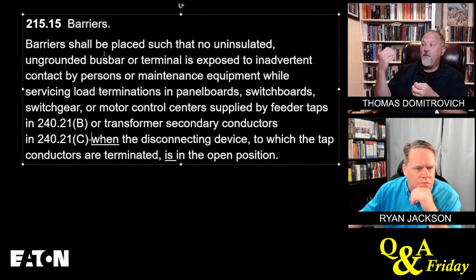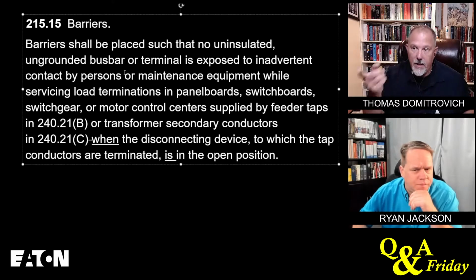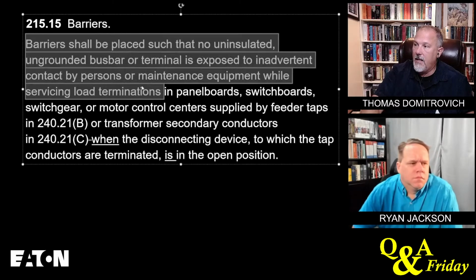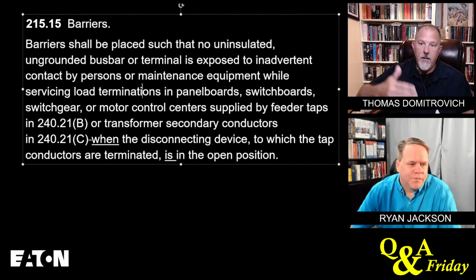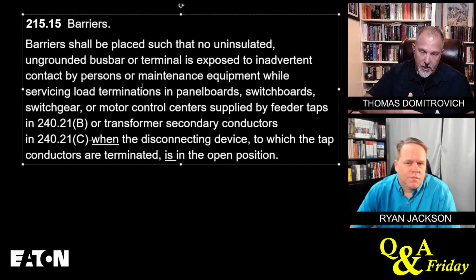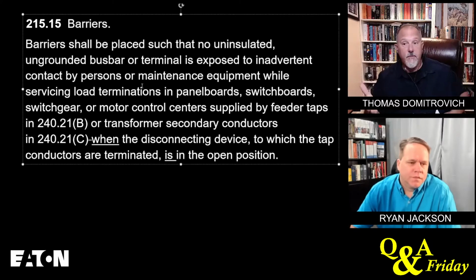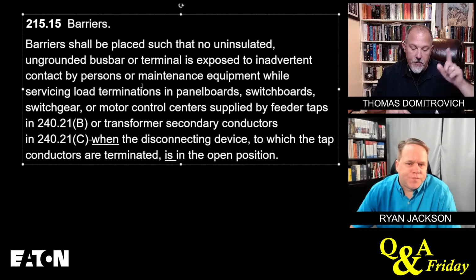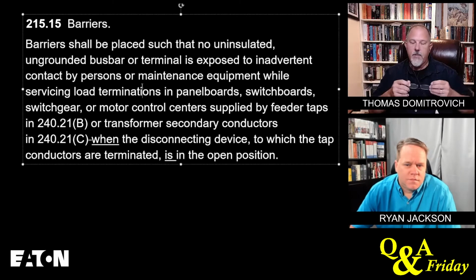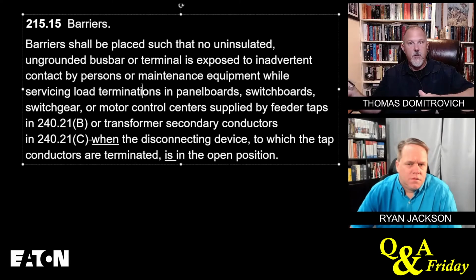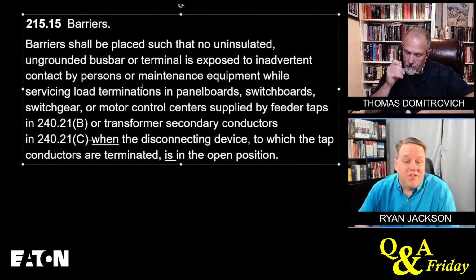And you supply them by feeder taps or transformer secondary conductors in C when the disconnecting device to which the tap conductors are terminated is in the open position. So I was focusing, and what I think you and others pointed out was that it doesn't say anything in here about energized, that only barriering off what's energized when that main overcurrent device is turned off. Because we took that from Article 230, if you remember, I can't remember what section, but we have similar language, but the parent text included the energized part. Okay, yeah, that's in 230.62C, I think.